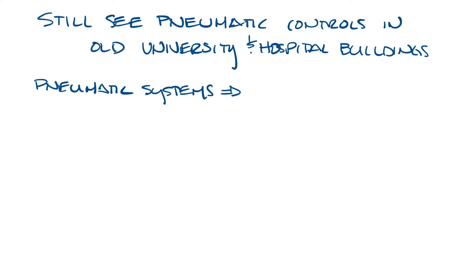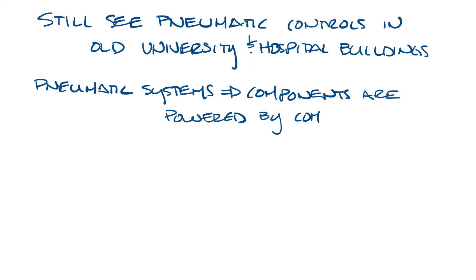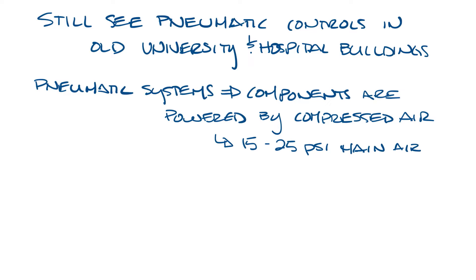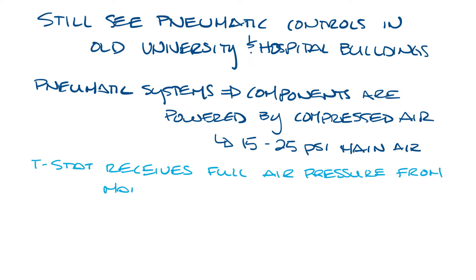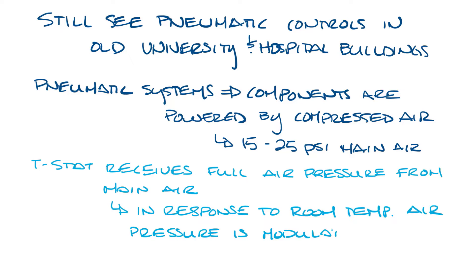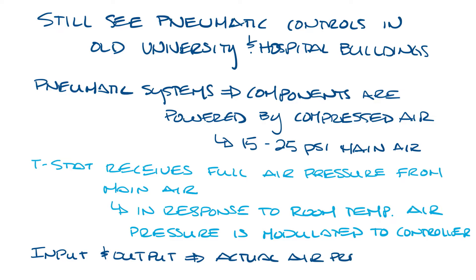In a pneumatic system, the components are powered by compressed air, usually 15 to 25 psi, from a main air system. The thermostat receives full air pressure from the main air supply. In response to room temperature, this air pressure is modulated to the controller, which controls the damper position. So when I talk about input or output relative to pneumatic controls, I'm talking about an actual air pressure signal.